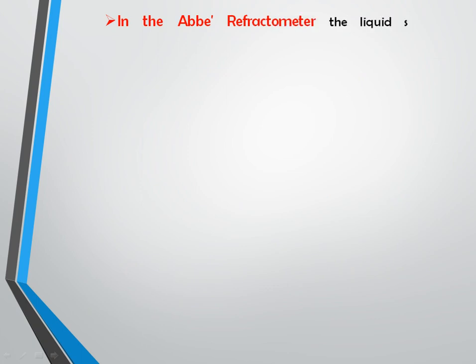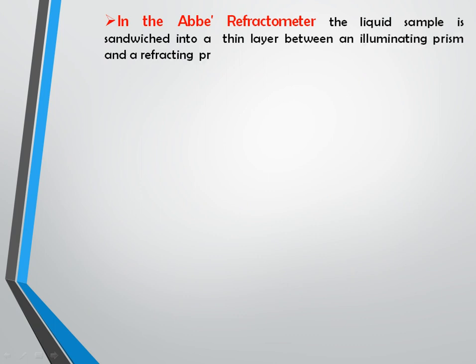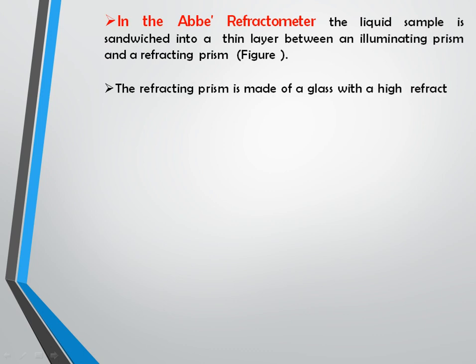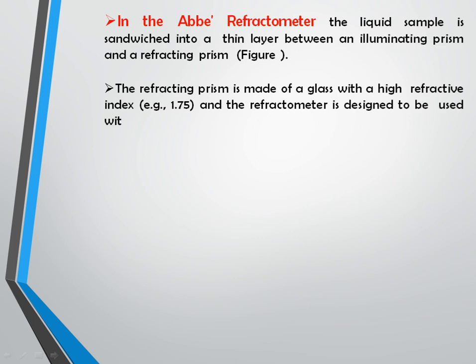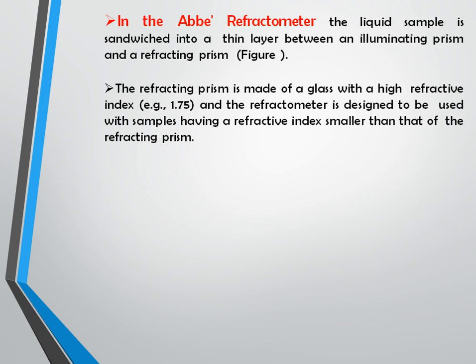Now we will move towards the instrumentation part — the Abbe refractometer, which is used to determine the refractive index of a substance. The liquid sample is sandwiched in a thin layer between an illuminating prism and a refracting prism. The refracting prism is made of glass with a high refractive index of 1.75, and the refractometer is designed to measure samples having a refractive index smaller than 1.75.